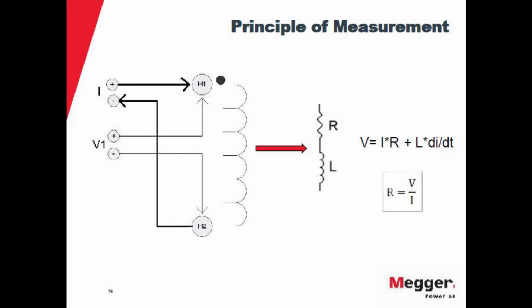And then the other aspect during the test is that basically you are charging this inductance with energy. After you complete the test, you need to discharge that energy. If not, that will kick back and you can have an arc, or you can have an accident with that energy. So the instrument that you use to perform a winding resistance test has to have the ability to discharge the energy from the transformer. So that's why you have to use a specific instrument for that.